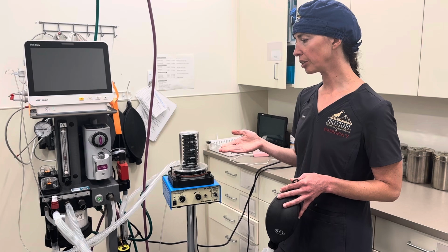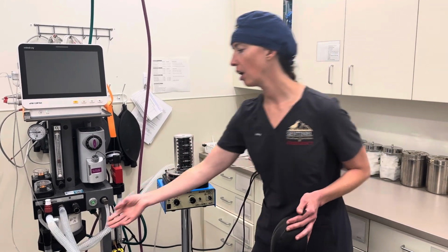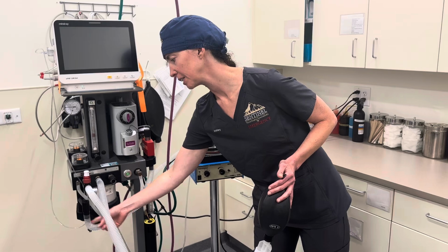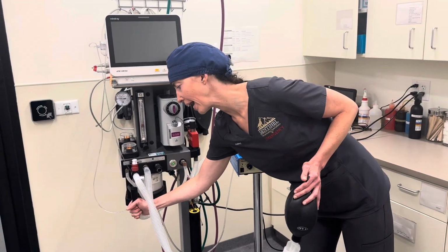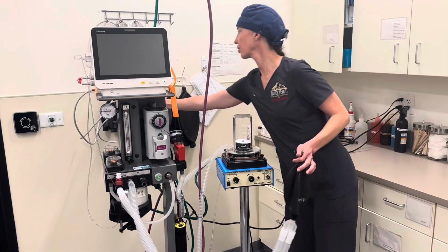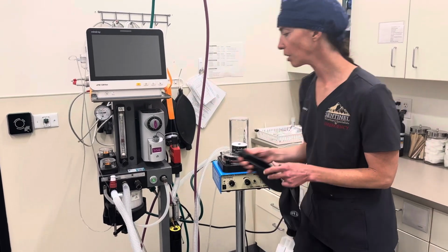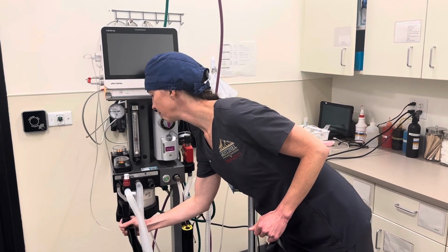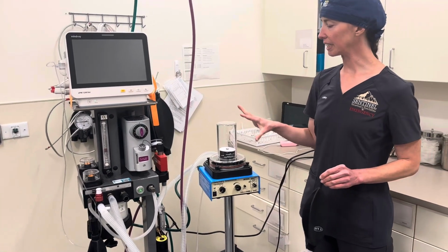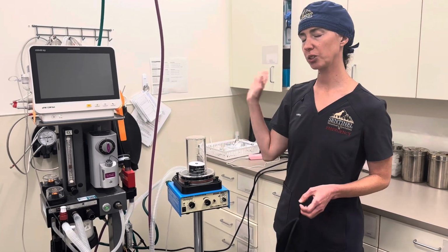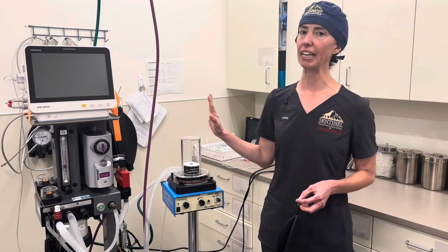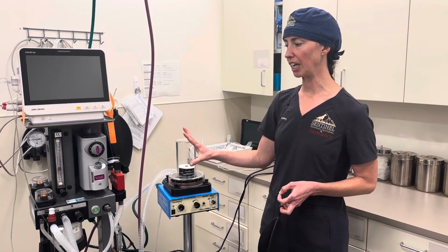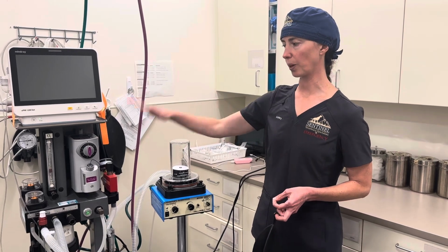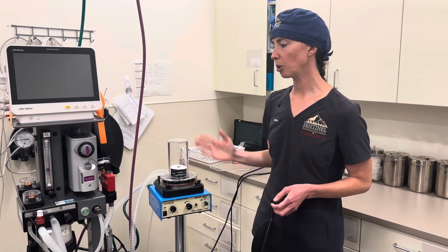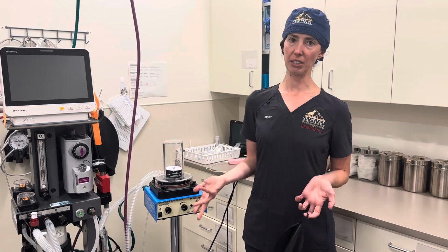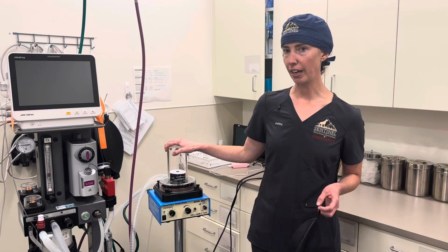And so then what we're gonna do is we're gonna put our rebreathing bag right here. So when we set up the ventilator, this basically became our reservoir bag, and now we wanna take them off the ventilator. So I'm gonna grab another bag back here, and we're gonna put that back on this machine. And the way this machine is set up, it's basically a dual circuit scavenge, so you don't have to disconnect or reconnect any scavenge on the back of this machine. It's already set up to be scavenged whether you use this machine or this machine. And so basically now our patient is set up to spontaneously ventilate, and they're disconnected from the ventilator.